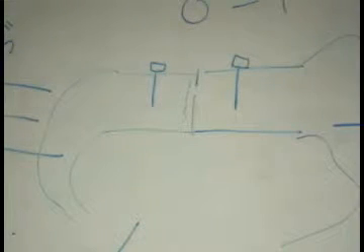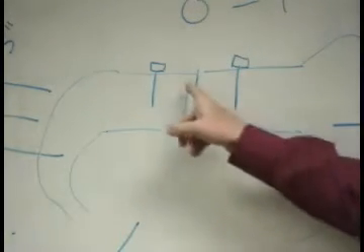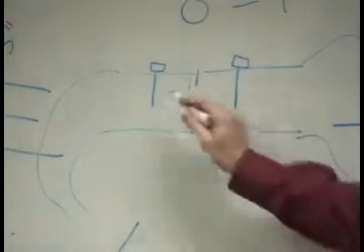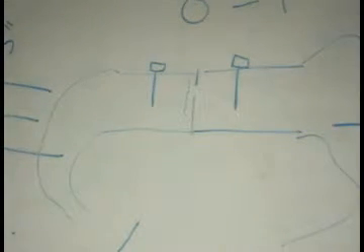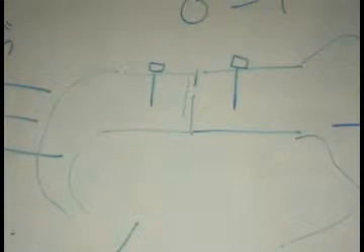They know the exact area of that orifice, and they know exactly how much heat that heater is putting out. So they measure the difference in temperature and calculate how much air is passing over that heater. That is the way that thing works.